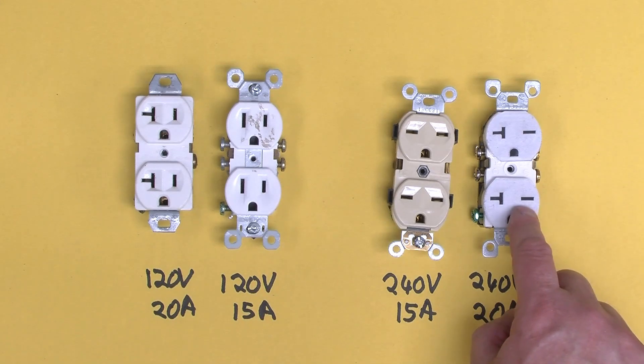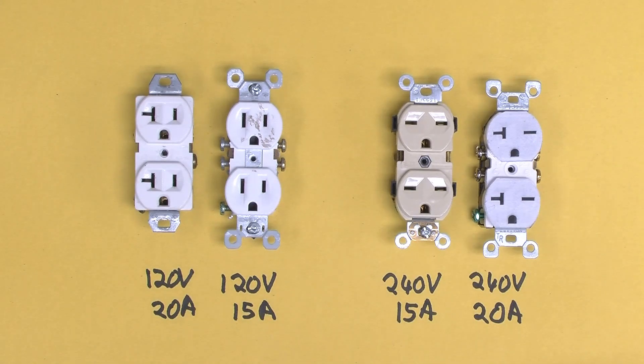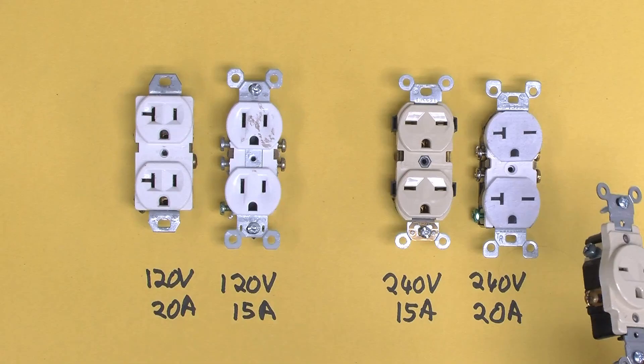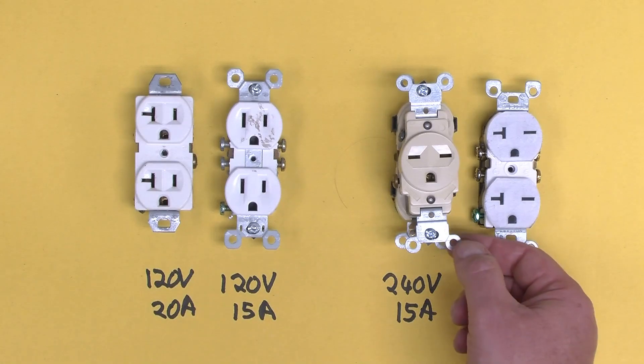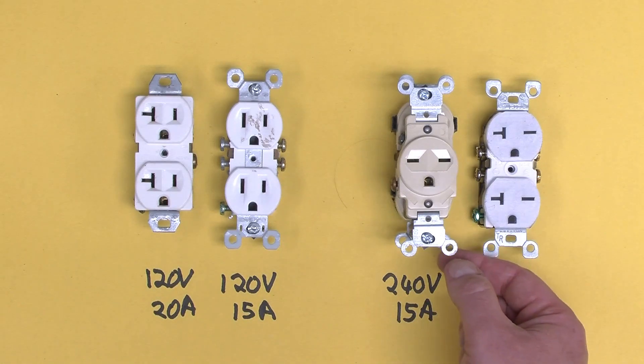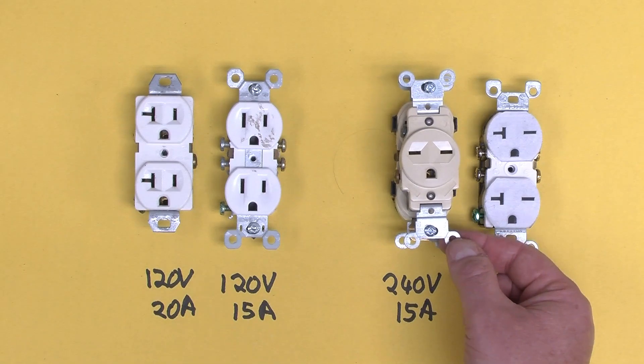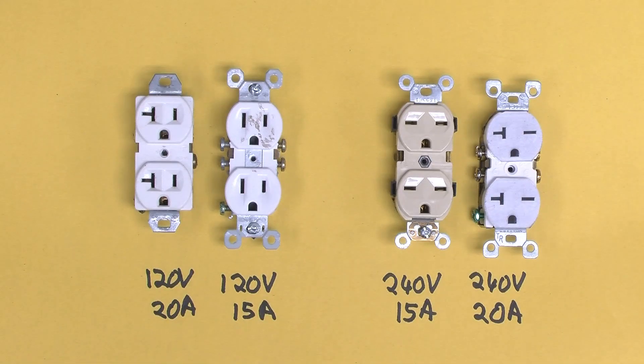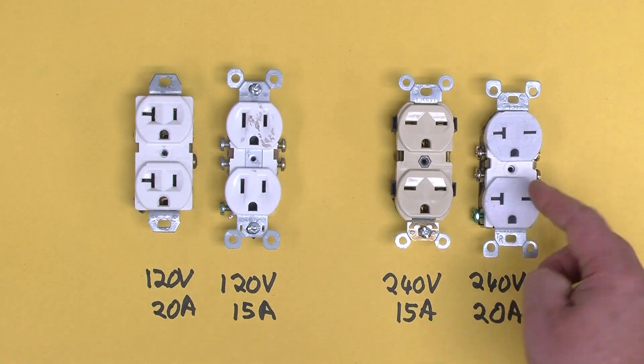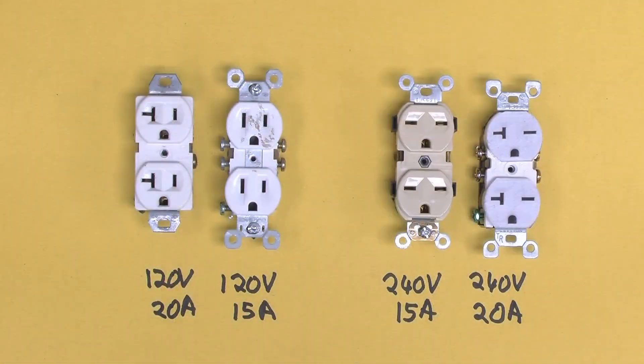I should point out that these two duplex receptacles are actually somewhat rare, and that's because they are most often replaced by one of these receptacles, a single outlet receptacle. Typically, if you're installing a 240 volt line somewhere in a North American building, it's for one high-powered device. Same applies to the 20 amp version, and in fact, that's what I have set up for my compressor, as you can see here.